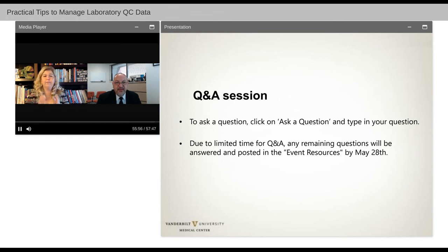Thank you so much. We have time for one more question. If the controls and analyzer are from the same company, can we use the ranges that are pre-printed that came with those controls? Keep in mind, those quality control ranges cover multiple, probably, models of analyzer that one manufacturer may be releasing or supporting, even though they are matched from the manufacturer with that particular model and make of analyzer. So those are usually much wider than are acceptable for clinical performance.